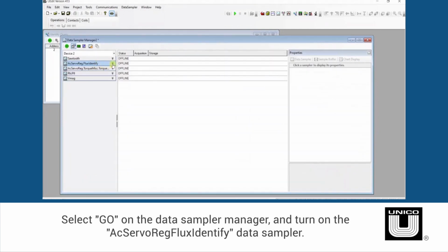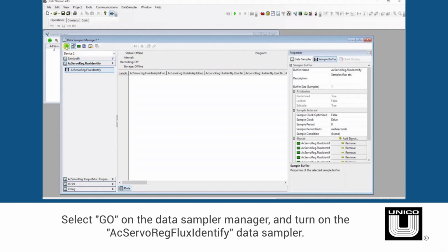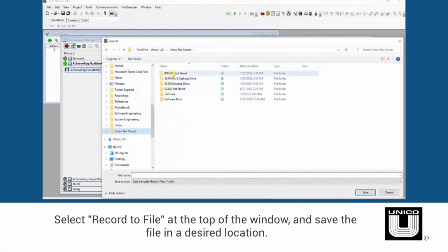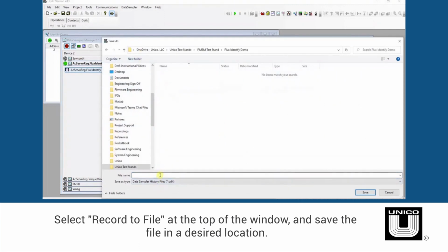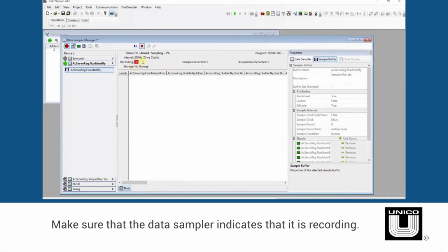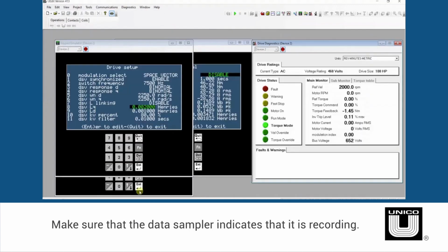Select Go on the Data Sampler Manager and turn on the AC Servo Reg Flux Identify Data Sampler. Select the Record to File icon at the top of the window and save the file in a desired location. Make sure that the data sampler indicates that it is recording. Once the flux mapping process begins, this will record all the data points for troubleshooting purposes.